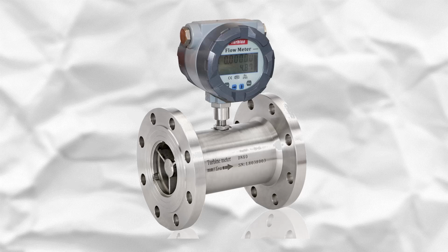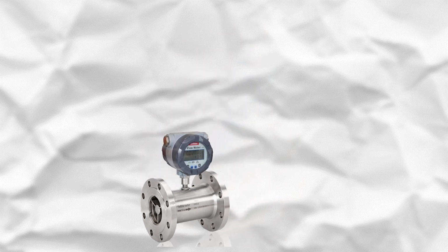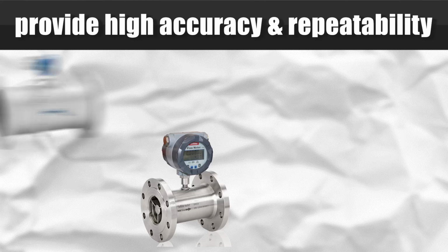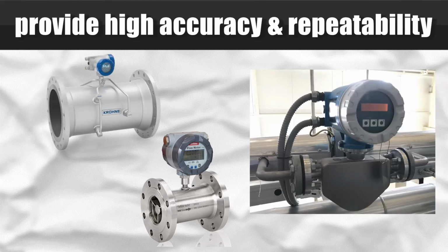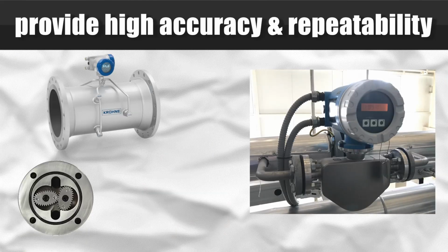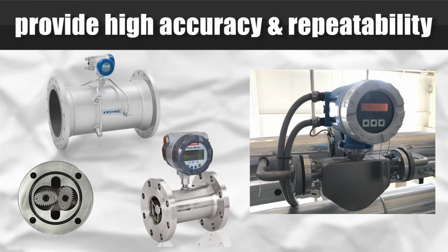To measure the flow of a fluid by means of a turbine flow meter, the fluid must be clean without any particles. In the metering system, we deal with ultrasonic, Coriolis, positive displacement, and turbine flow meters. These instruments provide high accuracy and repeatability.